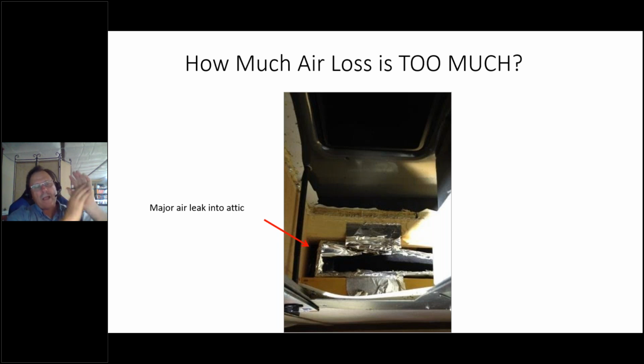The reason you measure your second air temperature reading is to make sure you're on the other side of this tape job, because you want that air to come down and go into the ductwork. If you get a bad delta, it means there's something wrong with the tape job, and the transition piece isn't allowing air to travel from the air conditioner into the ductwork. It's critical that we check these things.